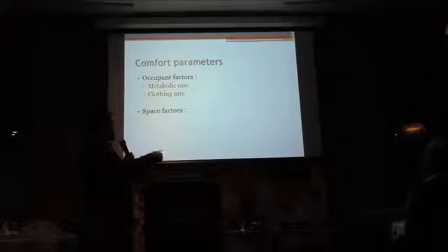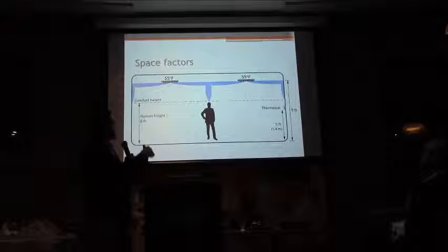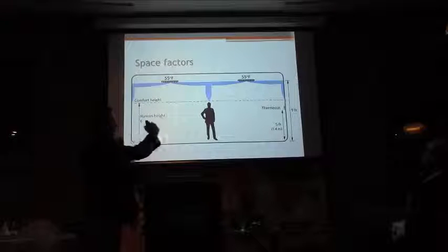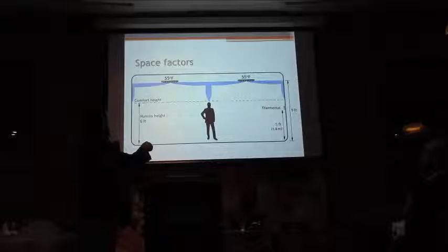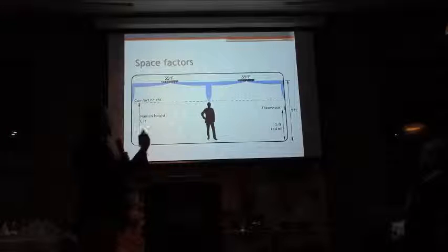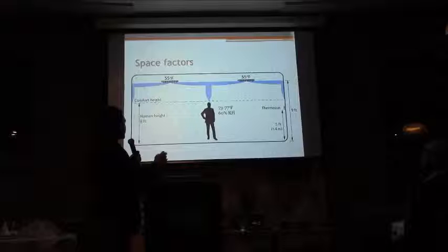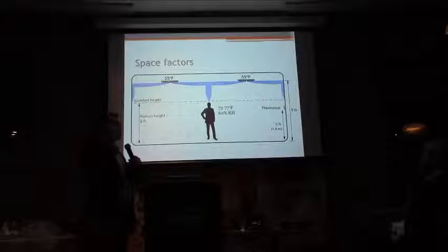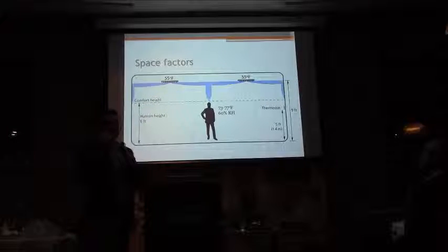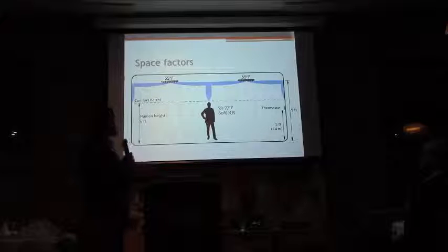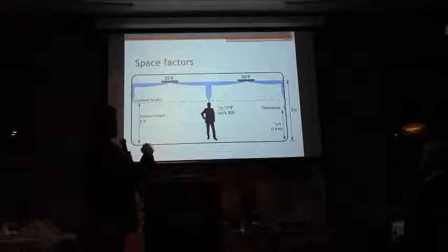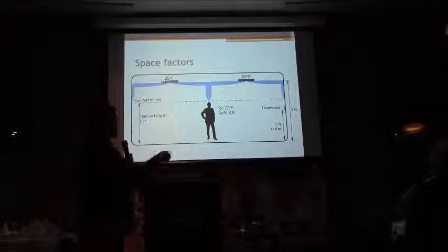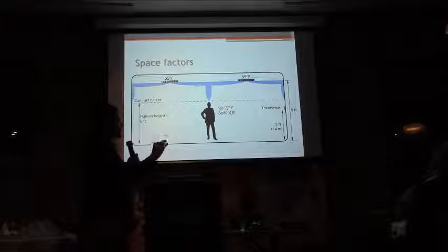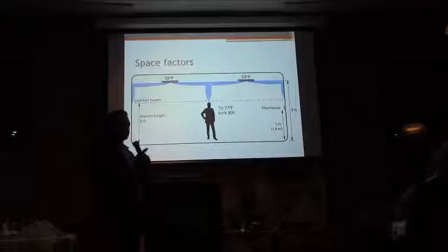The space factors, I'm going to present them in this graph here. This is a typical space. Your comfort height, as defined by ASHRAE, is always at 6 feet high. Whenever the air reaches that zone, you want to make sure the velocities are always under 50 feet per minute. Anything higher than that, you could feel the draft. So the space factors are the velocities of the air. You want to control your temperatures between typically 73 to 77 degrees Fahrenheit.